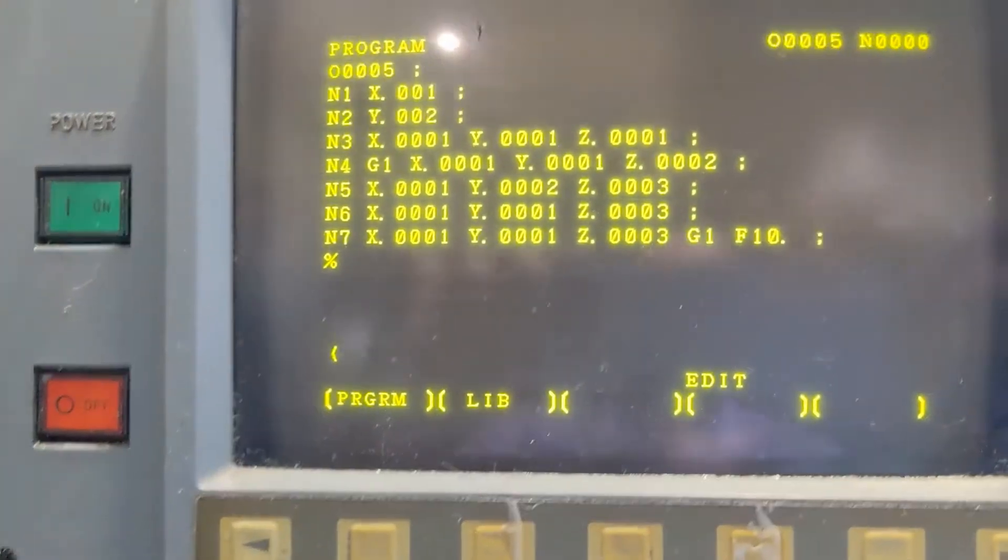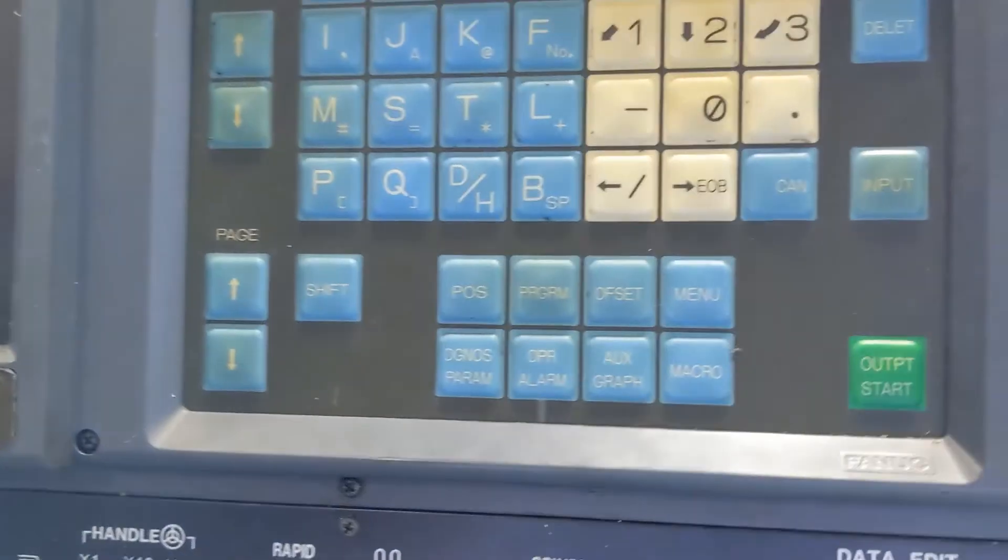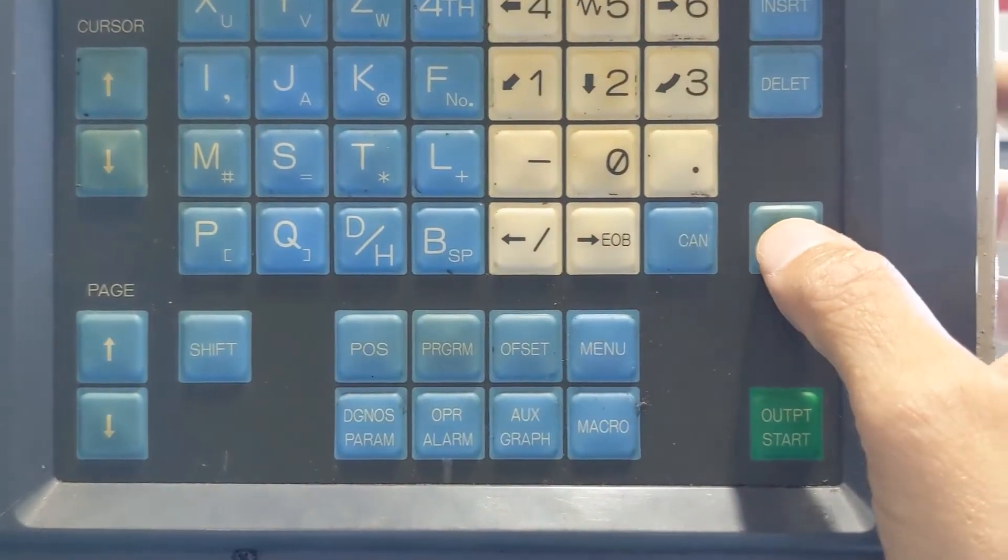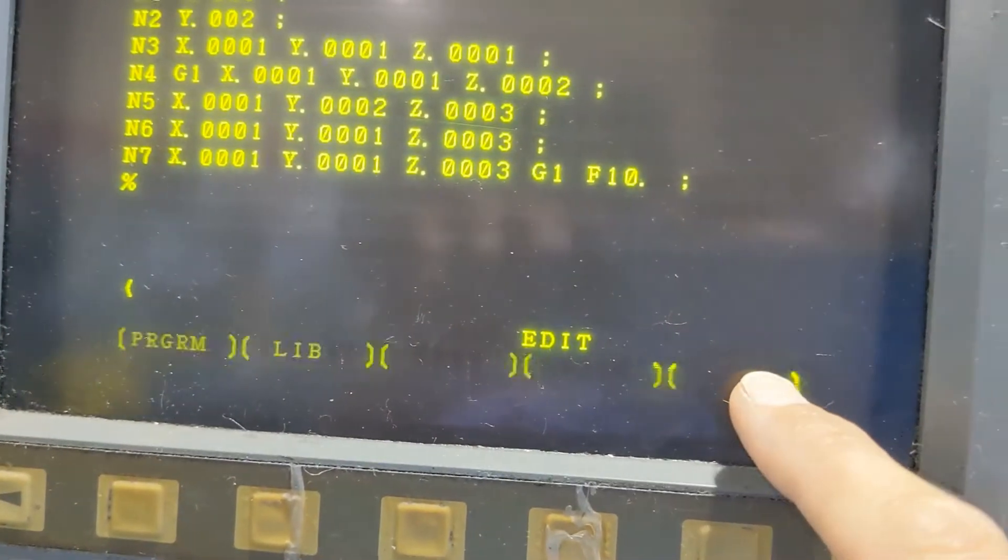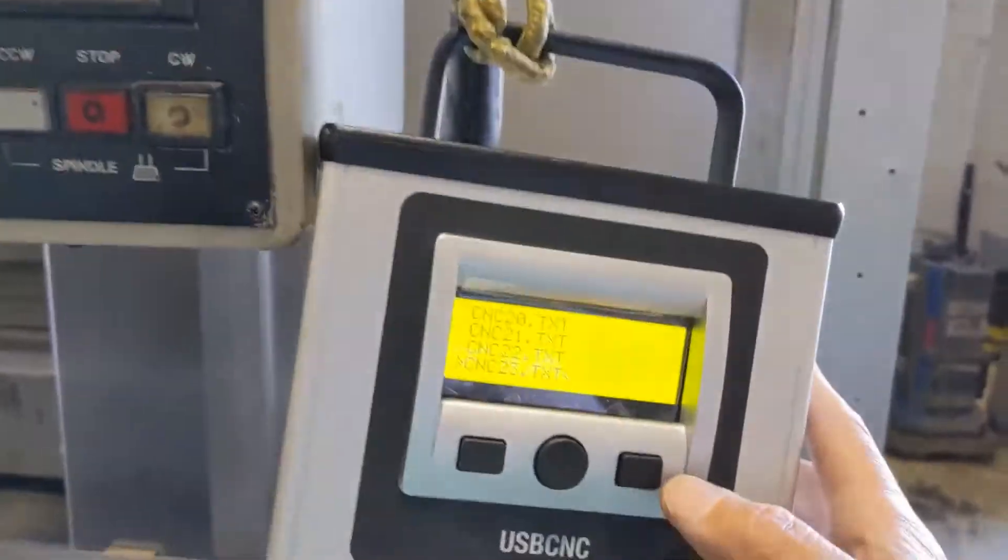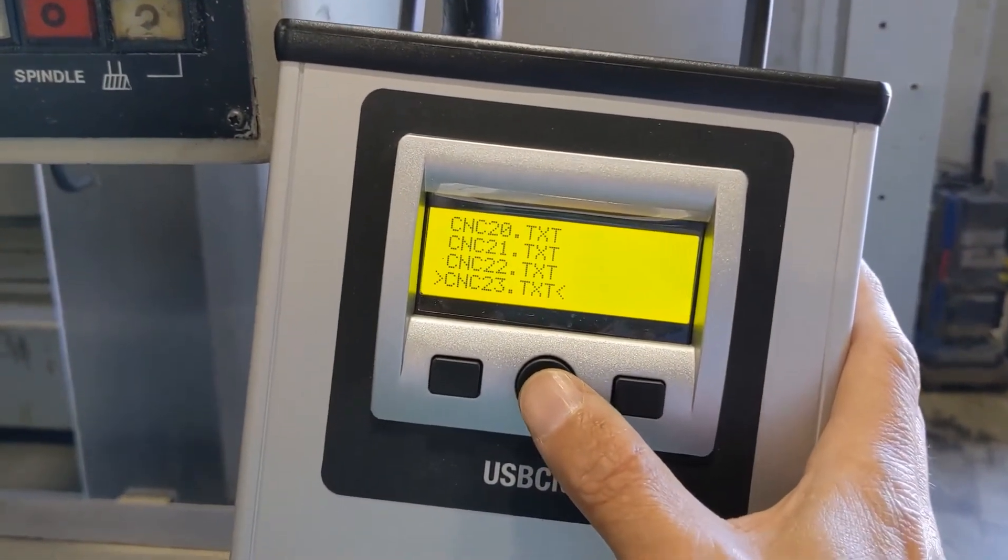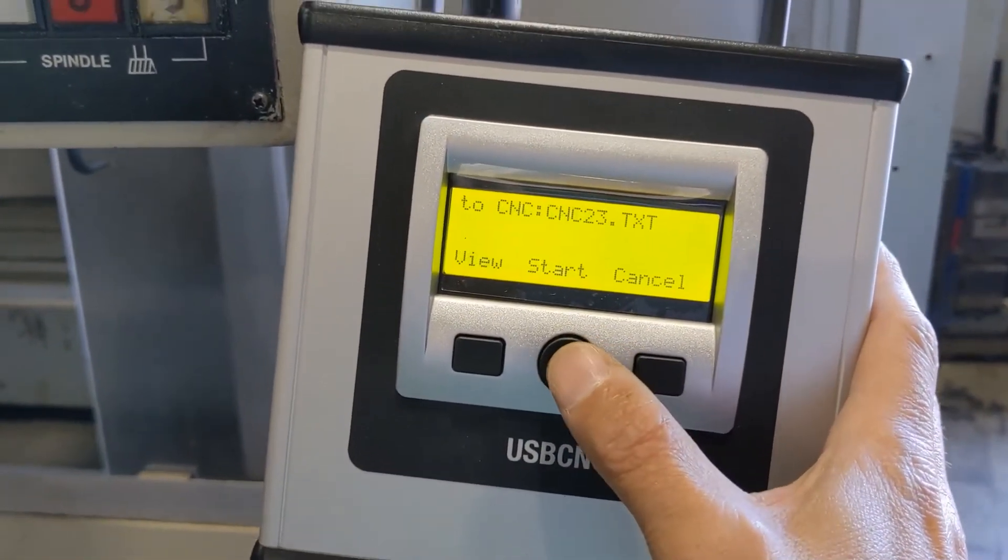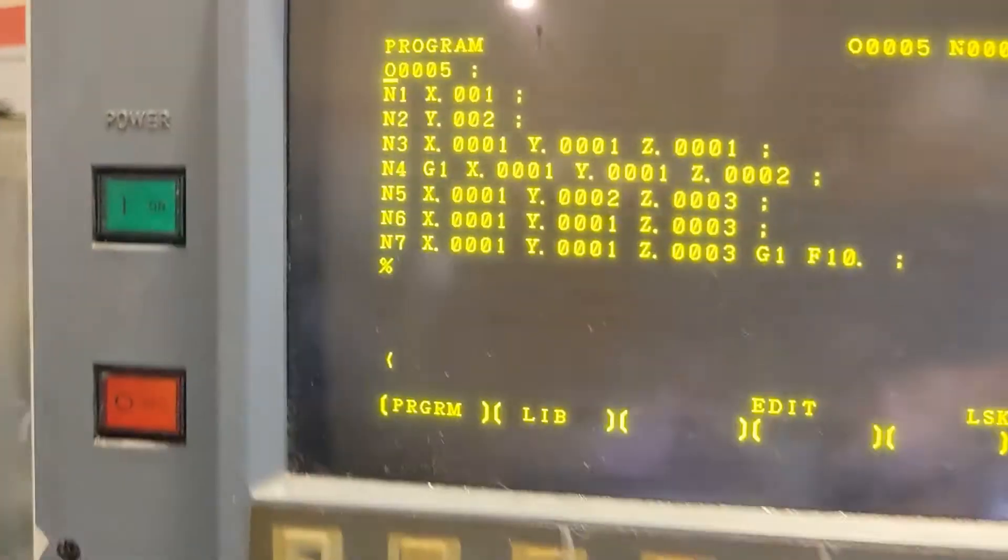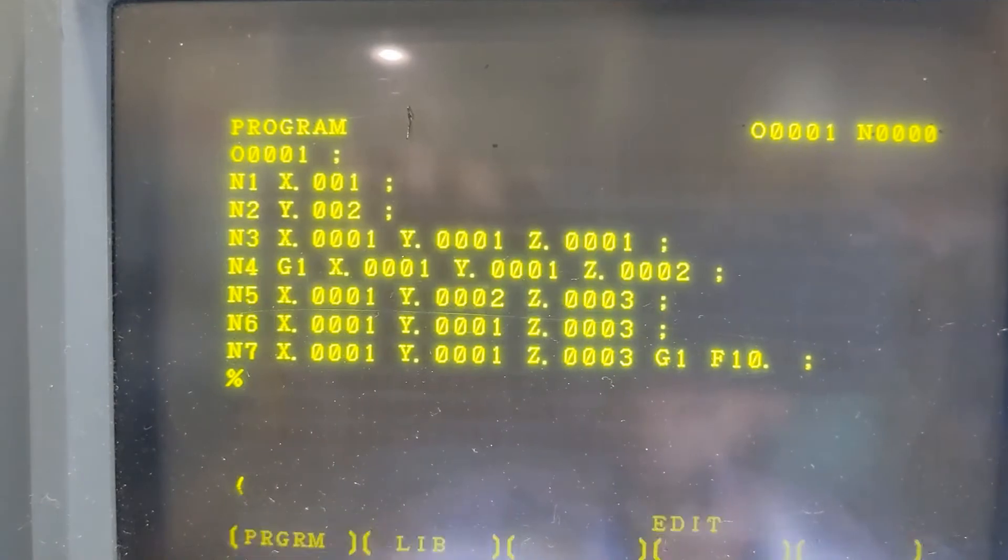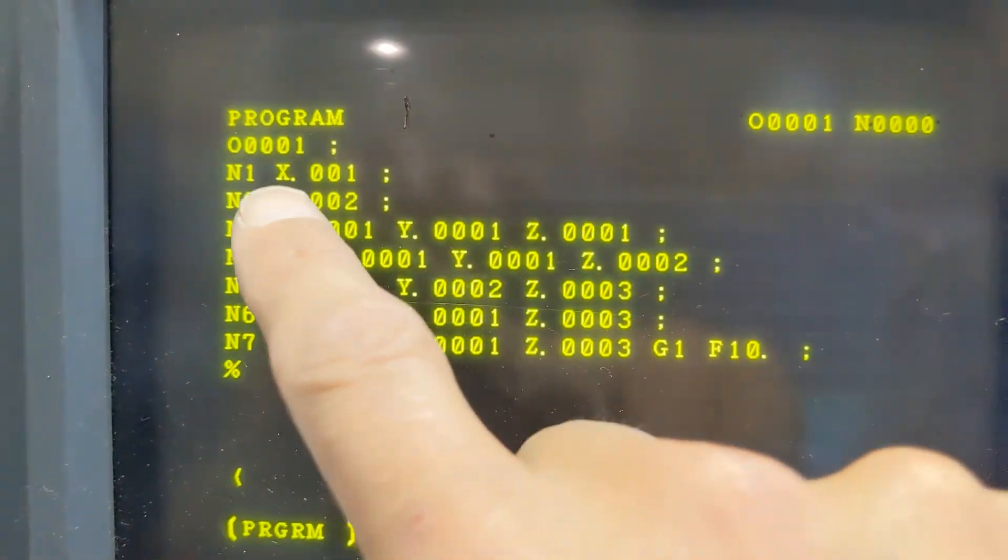So we're going to now load a program. The first thing you do is press the input key on the FANUC, which will then start the LSK. On the CalMotion box, you select USB to CNC, and we're going to send the same file we just received back. Once we press start, you'll see the program gets sent, and now it's program 001. We just sent that back into the FANUC's memory.